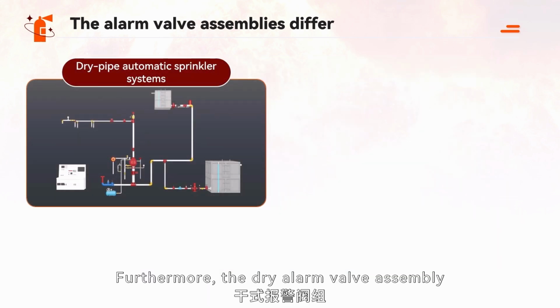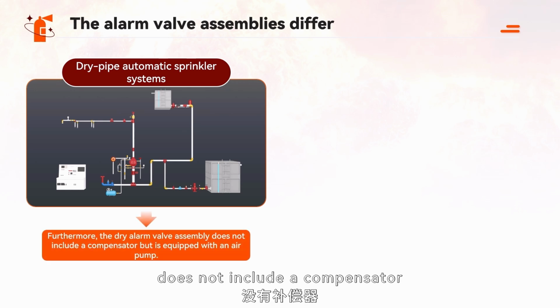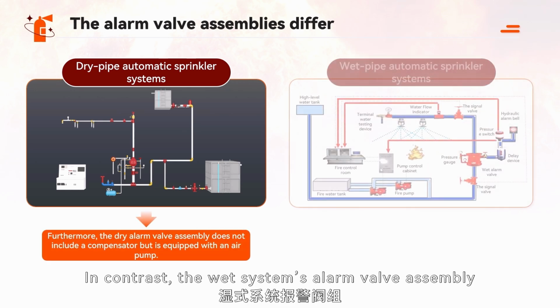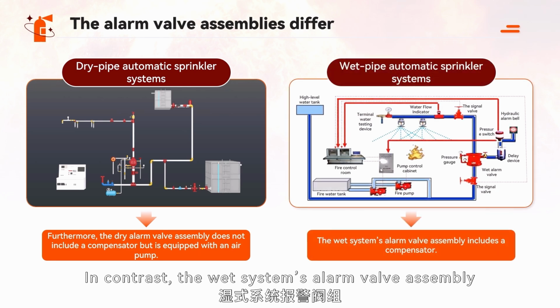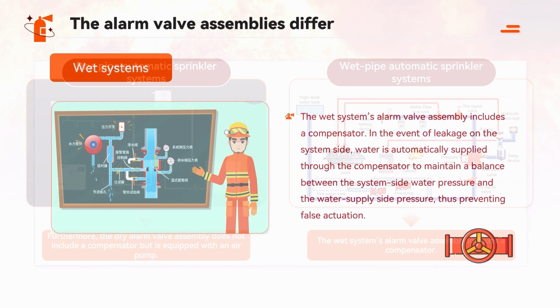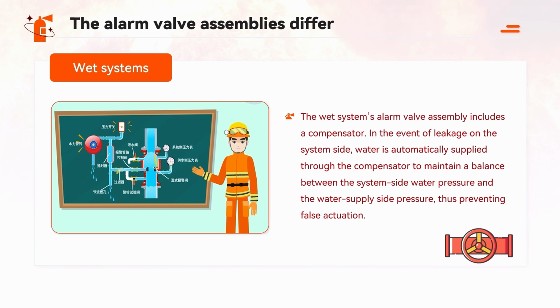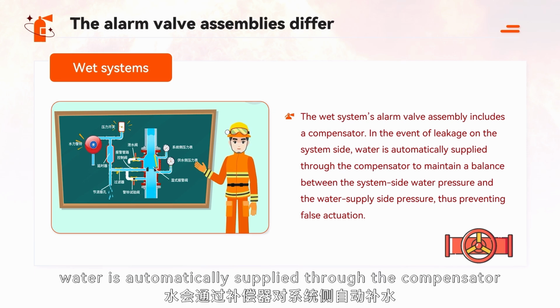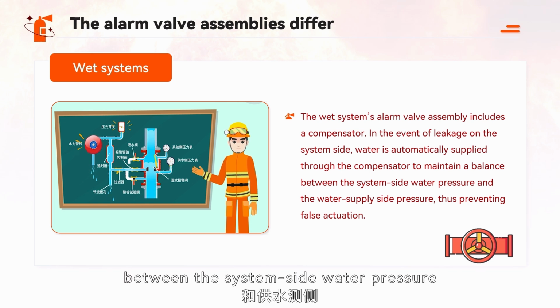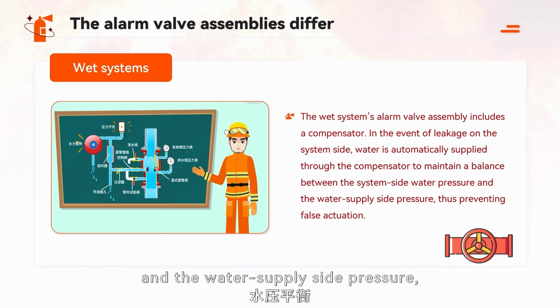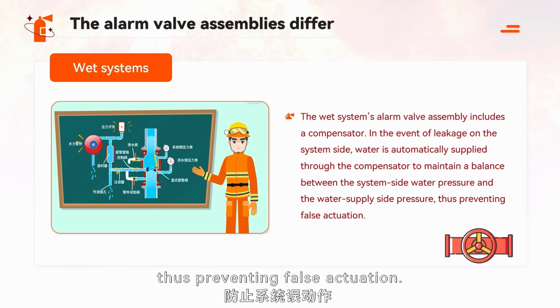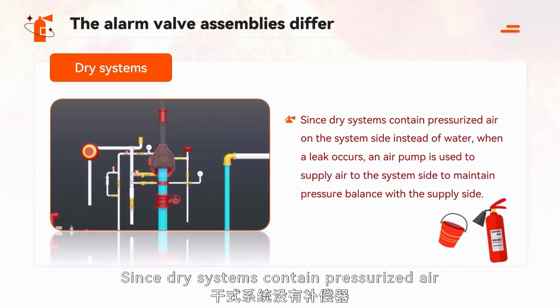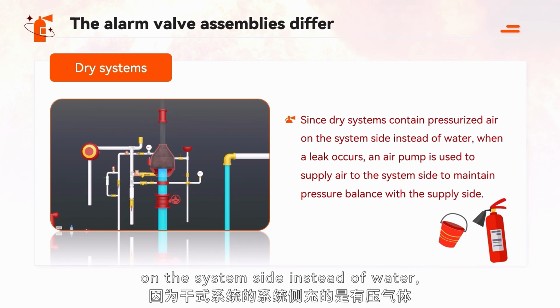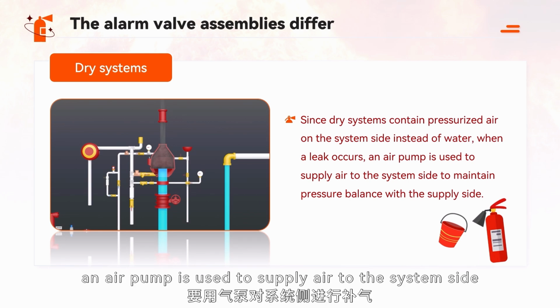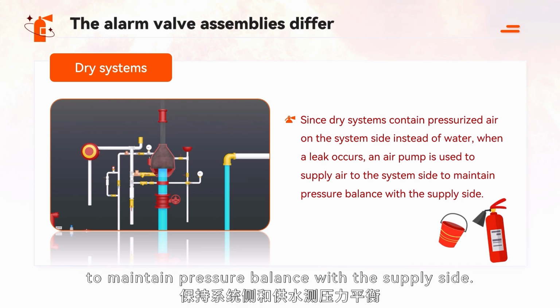Furthermore, the dry alarm valve assembly does not include a compensator but is equipped with an air pump. In contrast, the wet system's alarm valve assembly includes a compensator. In the event of leakage on the system side, water is automatically supplied through the compensator to maintain a balance between the system side water pressure and the water supply side pressure, thus preventing false actuation. Since dry systems contain pressurized air on the system side instead of water, when a leak occurs, an air pump is used to supply air to the system side to maintain pressure balance with the supply side.